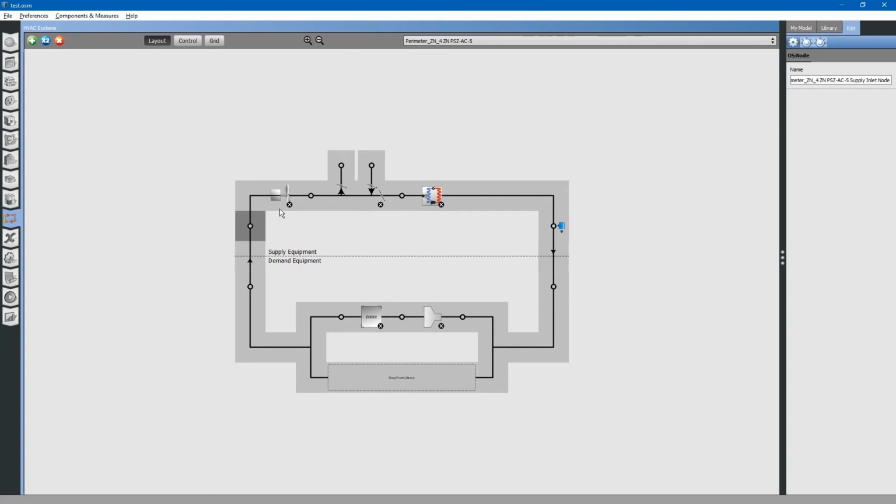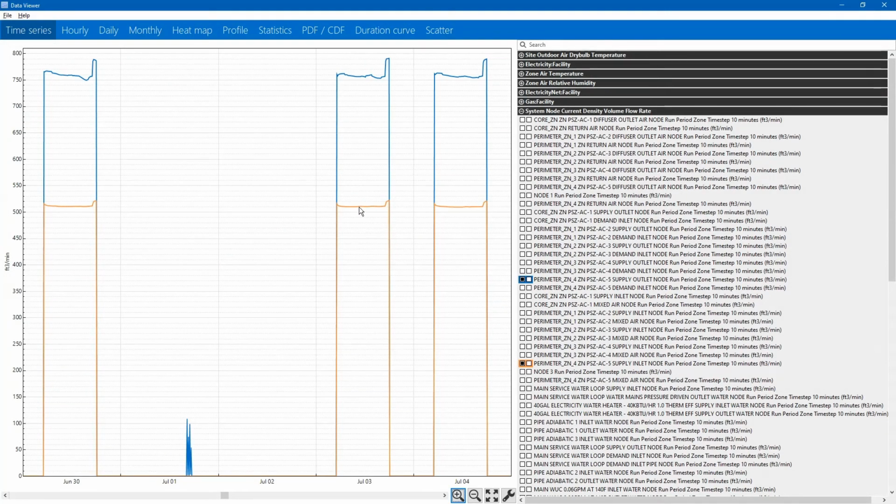So basically, these are not actually fans. They're not pushing air in the way EnergyPlus calculates it. EnergyPlus calculates fan energy use based on that airflow that the fan theoretically should have been flowing. So these fans don't actually push air into the zone, and the zone receives that air, not in the sense of how EnergyPlus calculates it. EnergyPlus back calculates it from the zone, and it tells the fan, you have to supply this amount of airflow, and this is how much energy you will use. So, with that said, you can see that the return airflow is lower than the supply airflow for that zone.